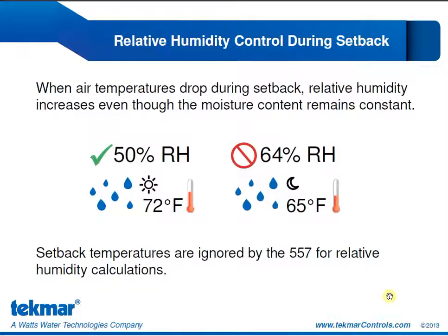As we discussed, relative humidity depends on temperature. So what happens at night if we set back? Let's look at the example. During the day, our air temperature is 72 degrees. And for the given amount of water vapor in the room, that could give us a relative humidity of 50%. If at night we drop down to 65 degrees Fahrenheit, that same amount of water vapor in the air would give us a relative humidity of 64%, because colder air can contain less water vapor. Now, if we used this value for relative humidity, it would probably trigger our dehumidifier to operate if we kept the default humidity maximum setting of 60%.